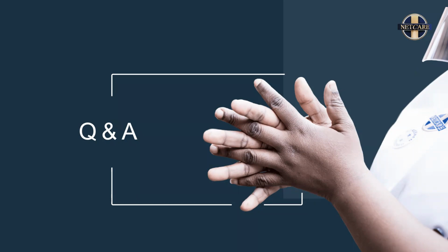But you can modify your air handling units to be full fresh air, which has been done in the second and third surge, and I'm reiterating this to the technical managers: go check this, make sure those recirculation dampers are closed, and that it's full fresh air systems as far as it goes in these ICUs, high cares, EDs, and high risk areas.